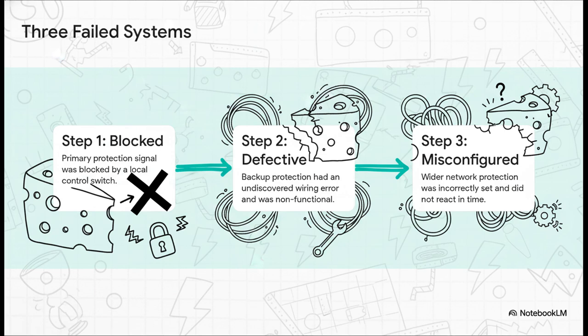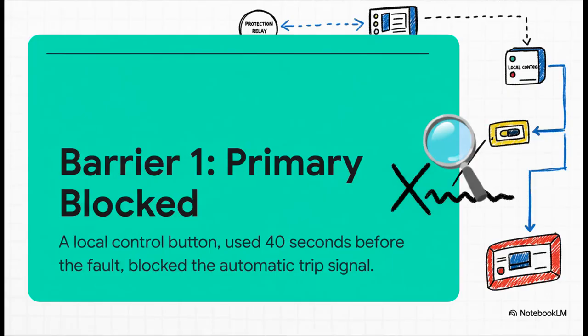First, the primary protection, which is your immediate local defense. Then, the dedicated backup, which is designed to kick in if that primary one fails. And finally, the network protection, which is the wider safety net from the feeding stations. Well, let's look at each one. Barrier 1, the main protection.